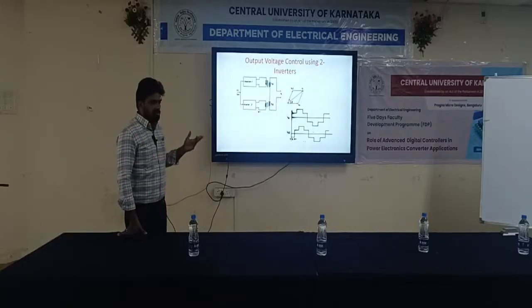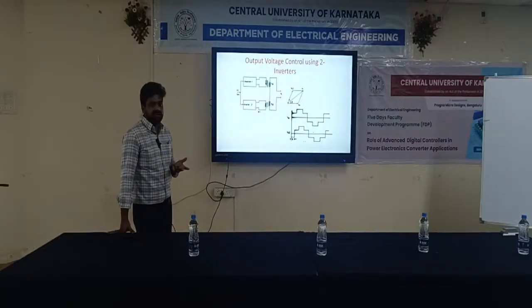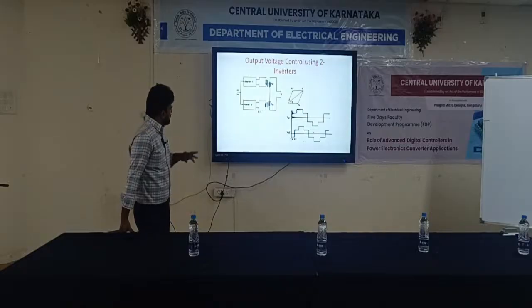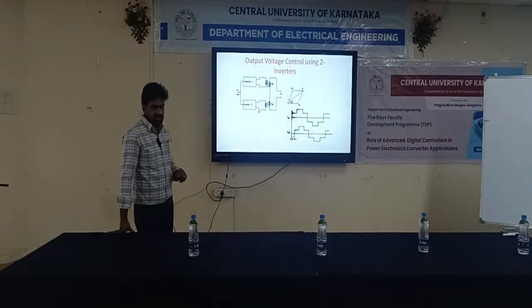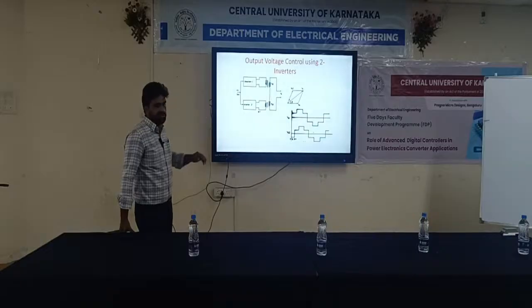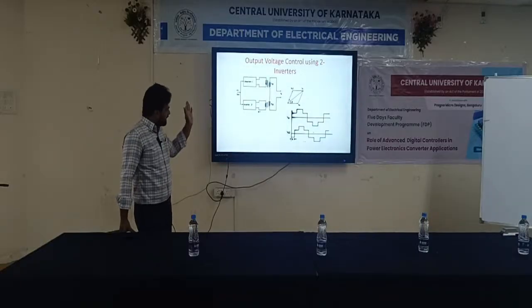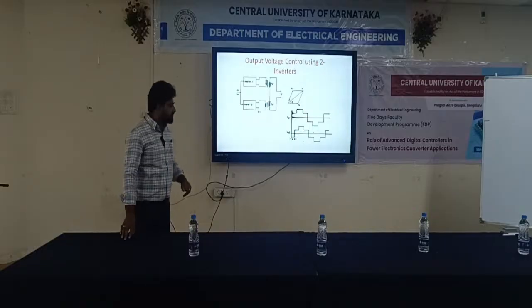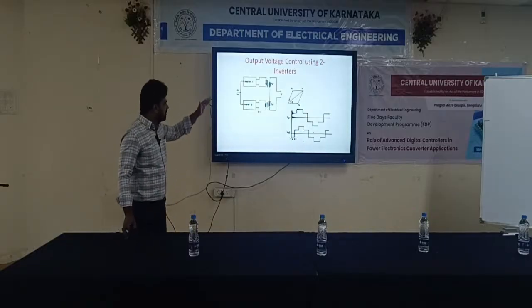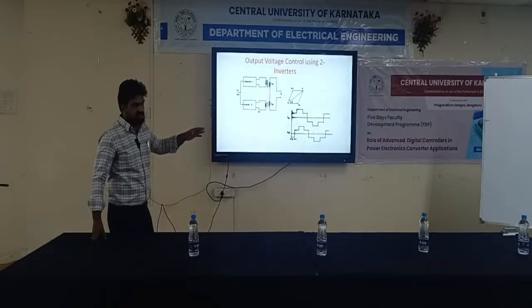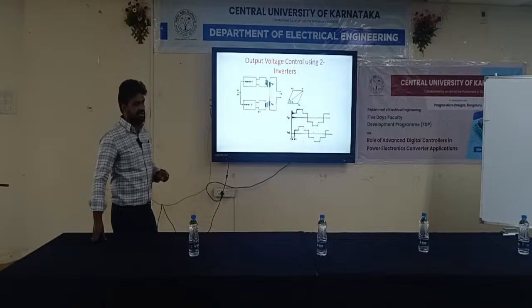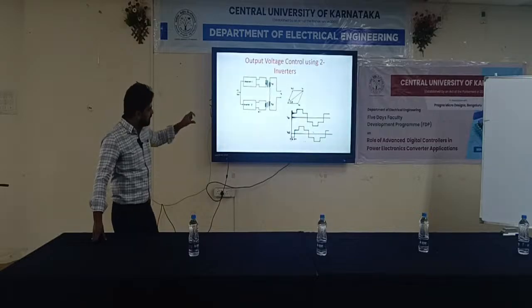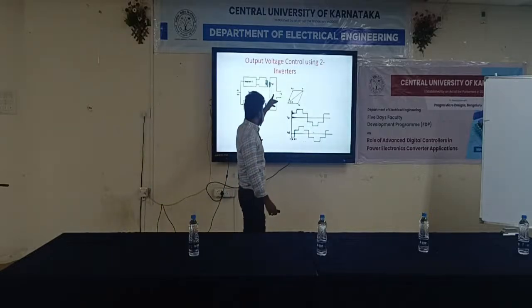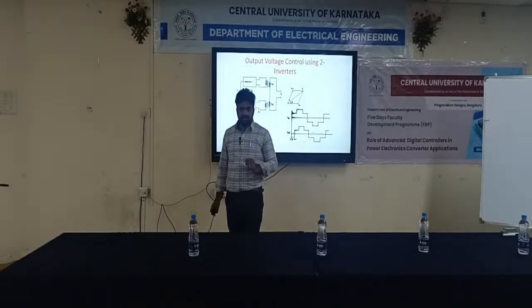Beyond that, we cannot be able to operate it. So what we need to do, we need to go for a multi-pulse inverter. So what we do, we can connect two inverters, which can be connected to a transformer, and they are coupled. The secondary side of the transformer is coupled, so that inverter 1 gives a voltage, inverter 2 gives a voltage, and both the voltages are induced in the secondary windings in series, and actually we will be able to attain a high voltage.